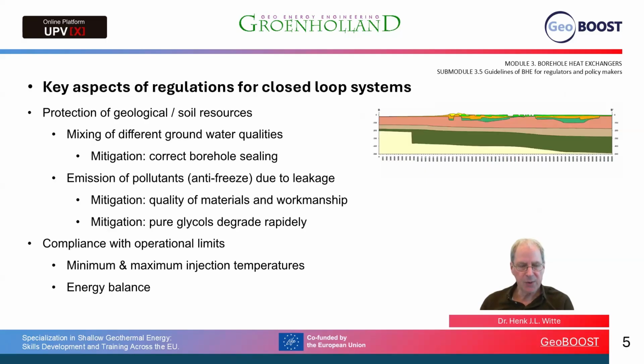Now, key aspects of regulations, when we think about what we want to regulate, what we want to check for closed-loop systems. First of all, of course, protection of the geological and soil resources, groundwater quality, and things like that. The main aspects here are that we want to prevent mixing of different groundwater qualities. In the little picture on the right, you can see a geological profile with a lightly colored gray area between a pink and a darker green area. And this is a clay layer between two different water-bearing formations. We want to prevent boreholes drilling through this clay layer and perhaps having the risk of mixing of groundwater. The mitigation here is to have a correct sealing of the borehole, usually through backfilling with clays and grouting of the borehole.